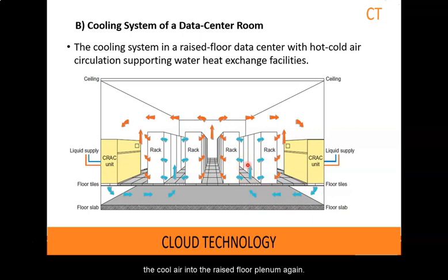Typically, the incoming coolant is at 12 to 14 degrees Celsius and the warm coolant returns to a chiller. Newer data centers often insert a cooling tower to pre-cool the condenser water loop fluid. The water-based free cooling uses the cooling tower to dissipate the heat. The cooling tower uses a separate cooling loop in which the water absorbs the coolant heat in a heat exchanger.